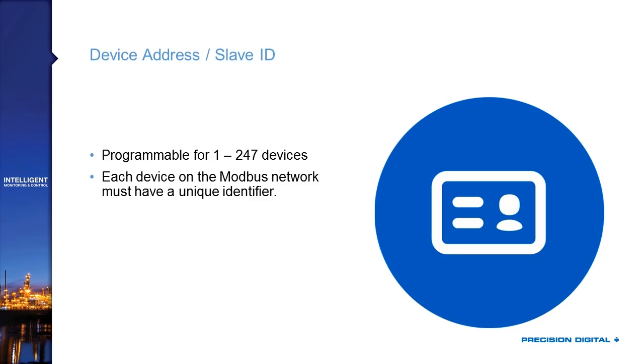It is absolutely critical that each device on the Modbus network is programmed with its own unique identifier. The analogy is a room full of people all trying to talk at once — if you don't know anyone's name, you can't address anyone specifically and everyone is just shouting. But if every person has a name and one person calls out names for each to speak, you get organized communication. The device address ensures that when a Modbus master sends a request, only the addressed device responds.